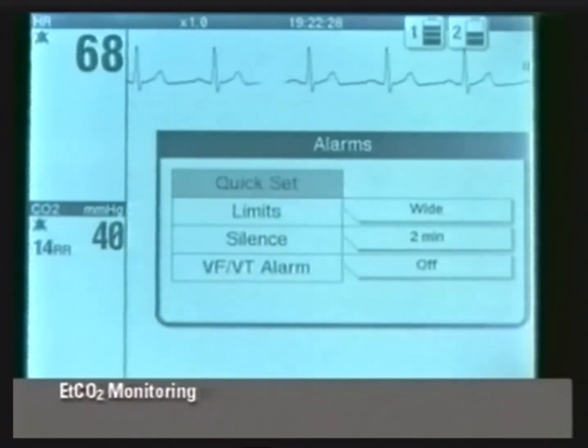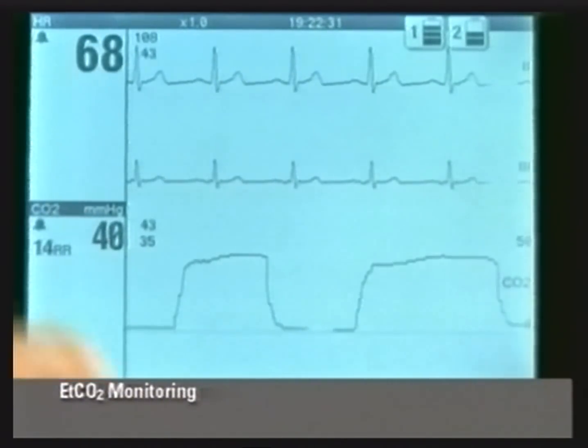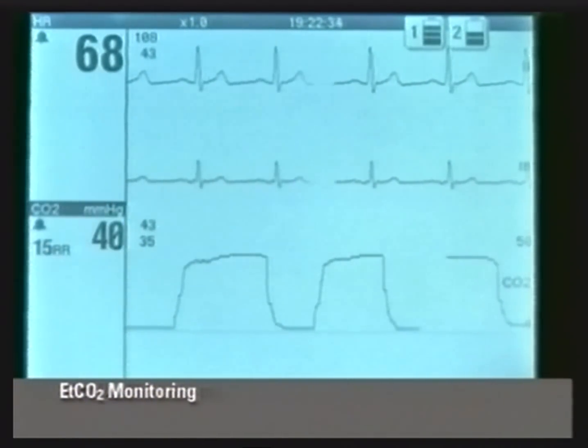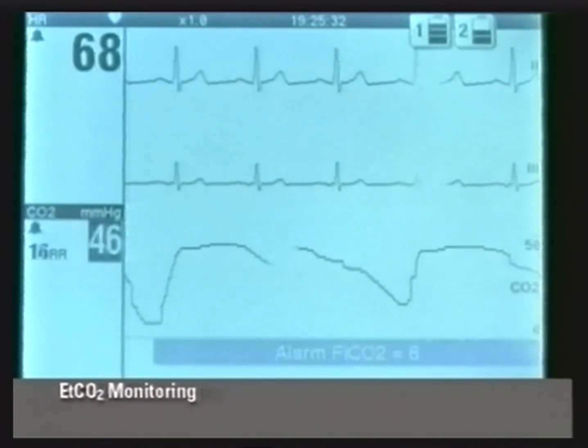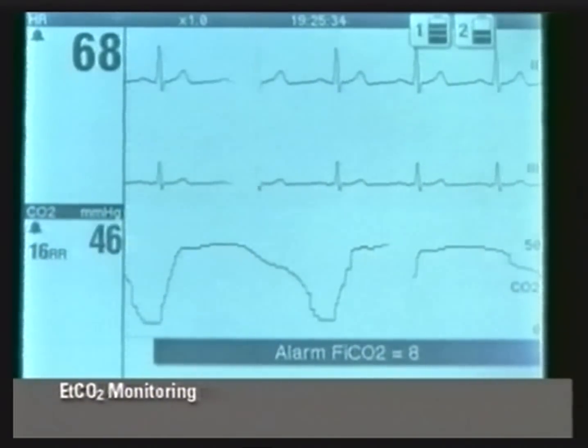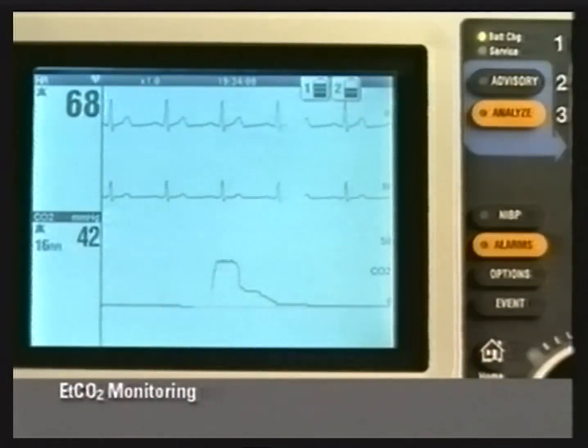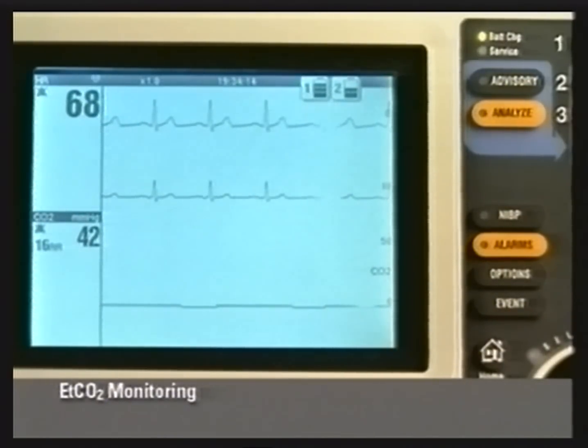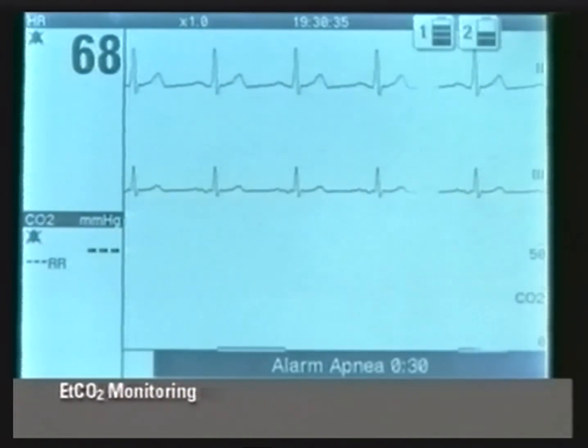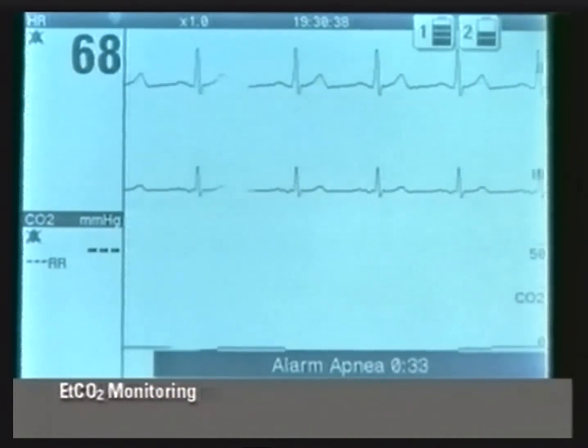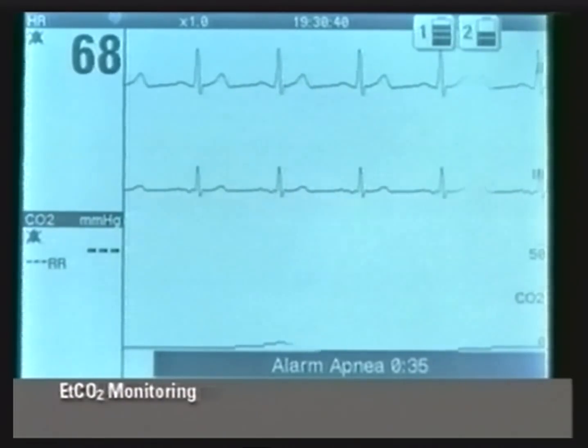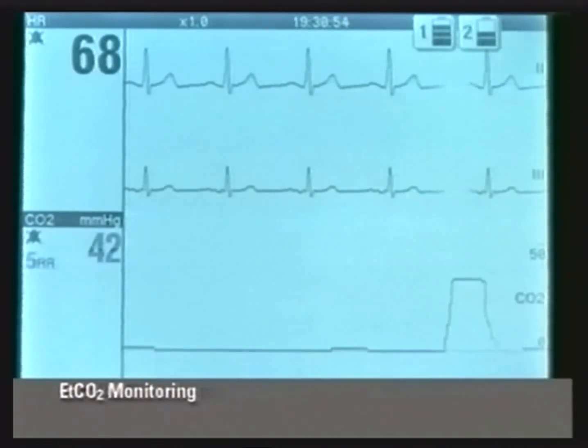When quick-set alarms are selected, the CO2 monitor provides high and low end-tidal CO2 alarms and a high inspired CO2 alarm. An apnea alarm is also provided, independent of the quick-set alarms, and is on whenever CO2 monitoring is in use. An apnea alarm will occur when the device has not detected a valid breath for 30 seconds. The alarm message includes the time since the last detected breath. The alarm clears once a breath is detected.